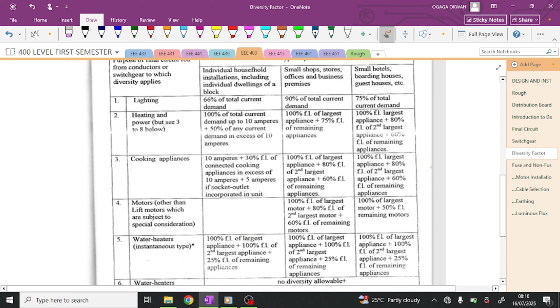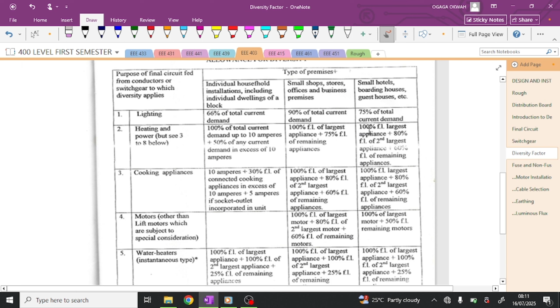So if you want to know, what's the diversity factor for hotels in terms of heating? Of course, I should get full load, 100% of the full load. That's for small hotels, for heating and power, heaters and things like that.